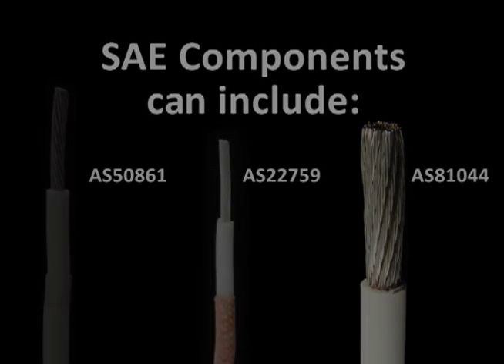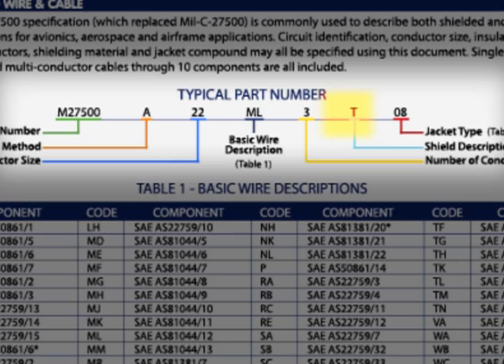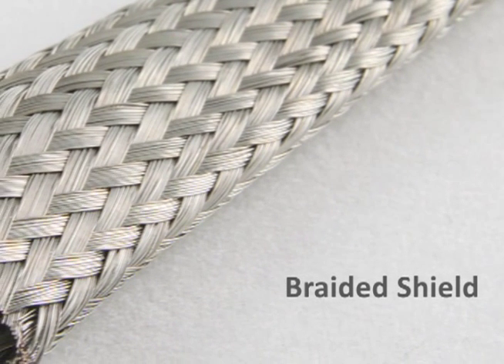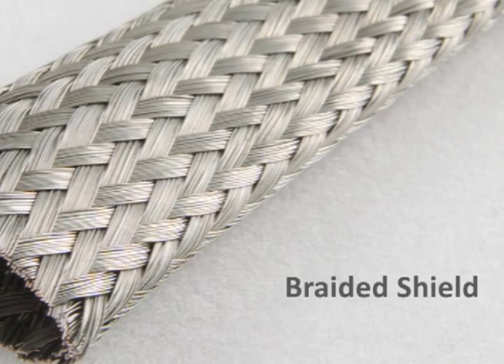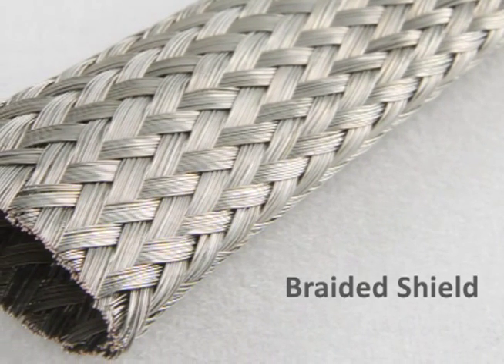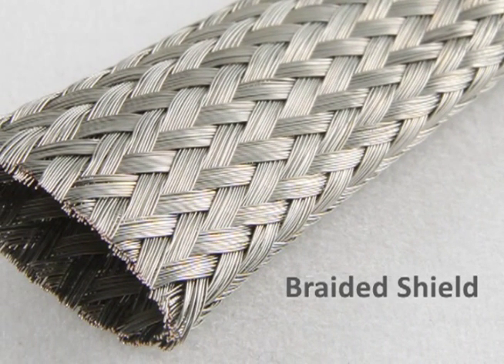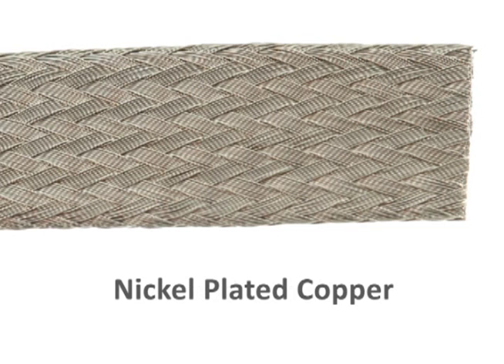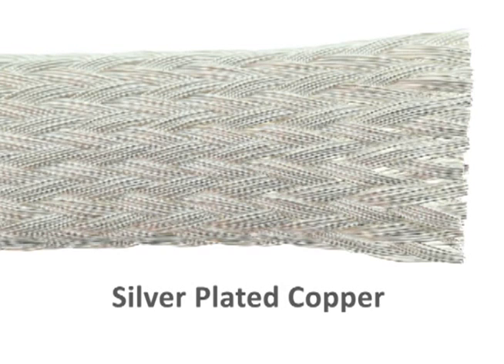Shielding is optional and is represented by a single-letter code in the part number. If the cable has a shield, it must be a closely woven braid with round or flat strands. Braids are available in a range of materials, including tinned, nickel-plated and silver-plated copper, stainless steel, and more.